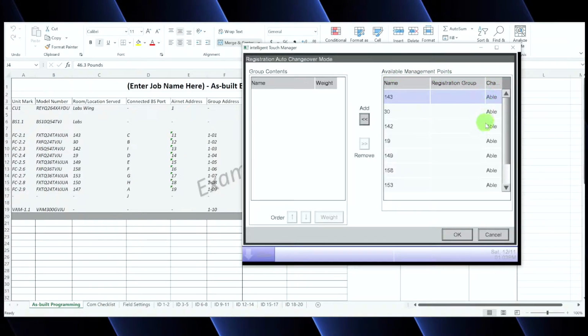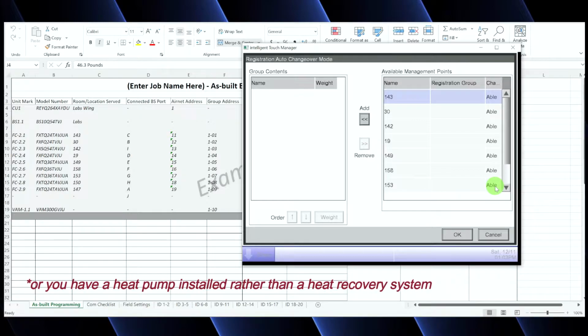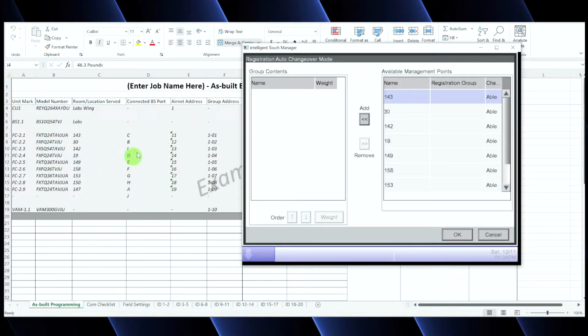It'll also show you if changeover is available. And basically, if it ever says not available or NA, it's usually because that indoor unit is paired to another indoor unit on the same port of a branch box, and the other indoor unit is the master for that port, which means that particular indoor unit does not have the ability to change the mode from heat to cool. In this case, if you recall from our previous video, all of our indoor units are on their own ports and they all have their own group addresses. So we're good to go as far as these units being able to heat and cool simultaneously, all on their own.